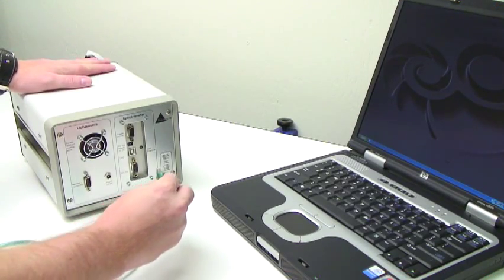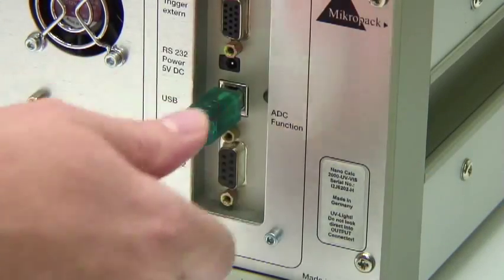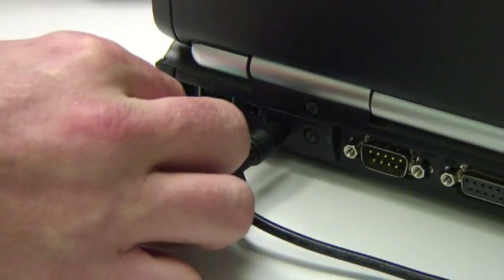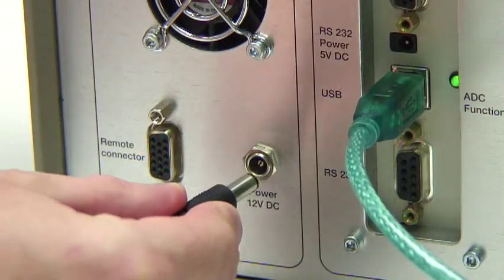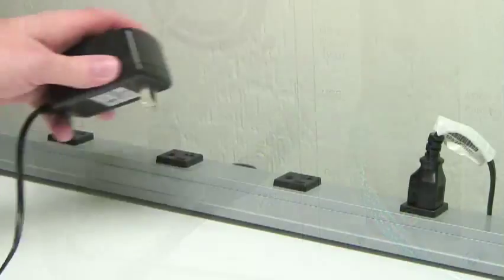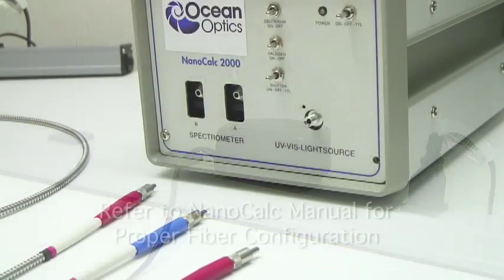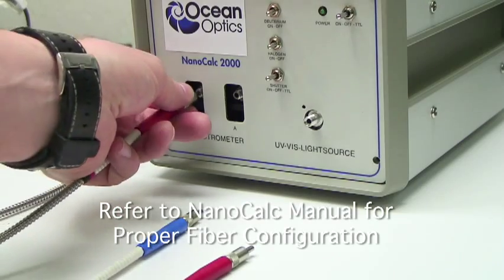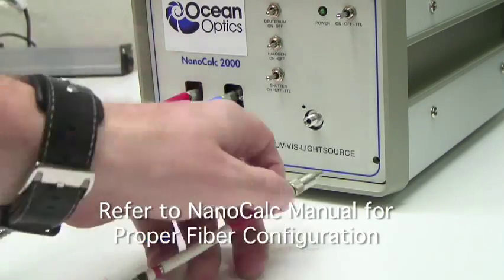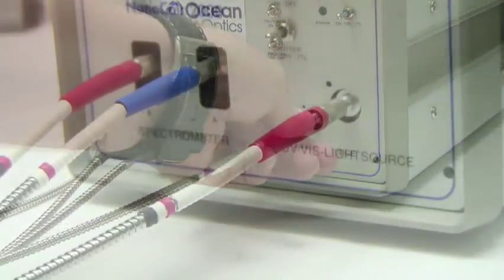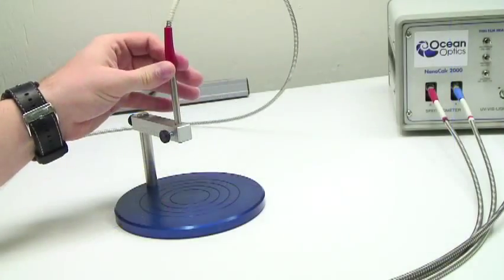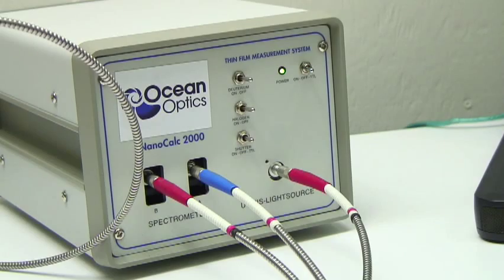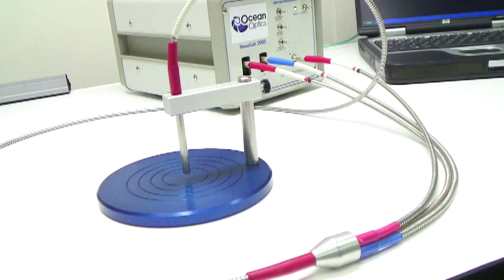Now connect the NanoCalc to your computer with the USB cable. You can also connect the power supply. Connect the fiber optic cable to the NanoCalc and to the fiber holder on the stage. You can now switch the power on to your NanoCalc. Your NanoCalc hardware and software are now successfully installed, and you should be ready to make your first measurements.